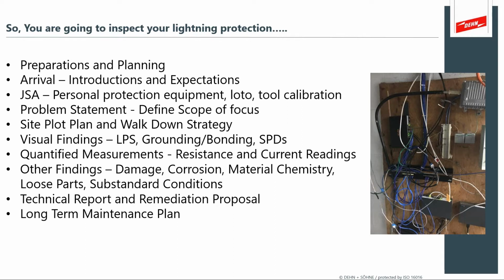What's our strategy? Starting from east to west, counterclockwise, top to bottom, have a strategy. Visual findings, that's where we start discovering things at the site. Quantified measurements, we're looking for the resistance and the current readings of the grounding system. And then other findings: miscellaneous things you're going to see, like damage, corrosion, material chemistry, loose parts.